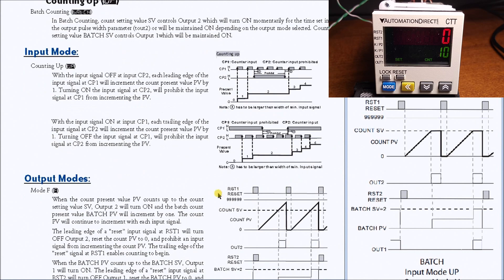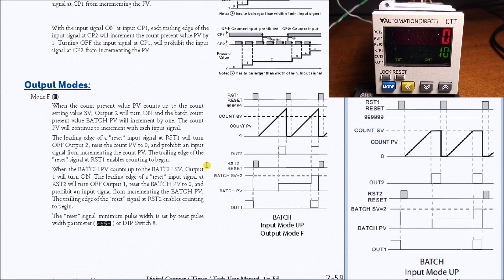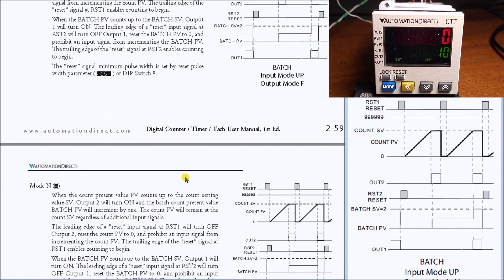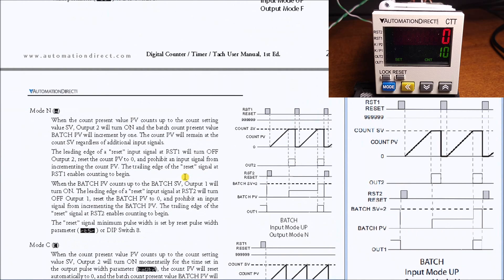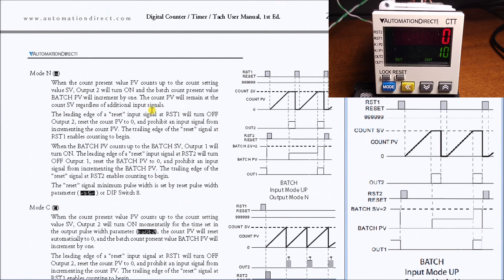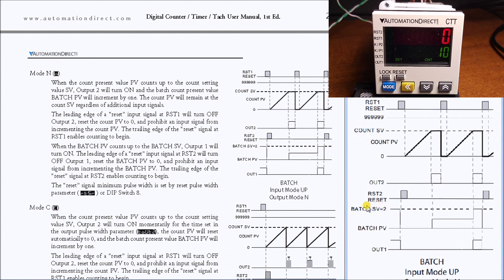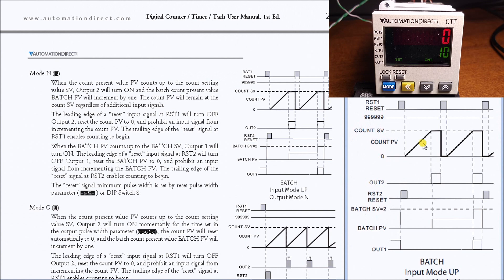In our output modes we have several to choose from. In my particular case here we're going to use output mode N. As we have two set points, we have set point one and set point two. The second one is for the batch set point we're going to set, and the first one is for our count set value. So it goes up, it will turn on the output and maintain that output on until we hit the reset.